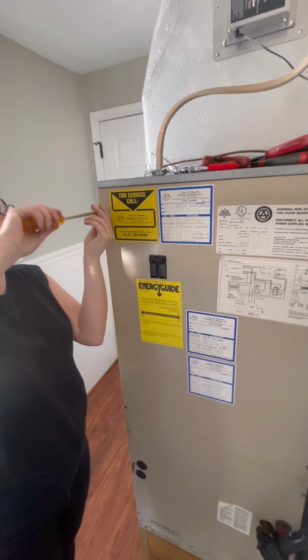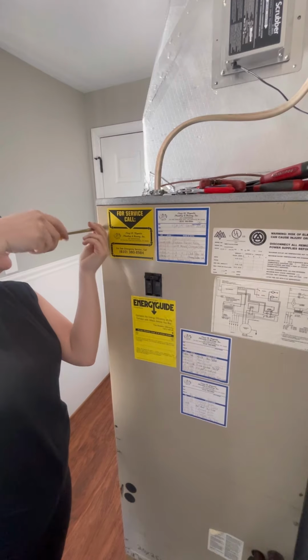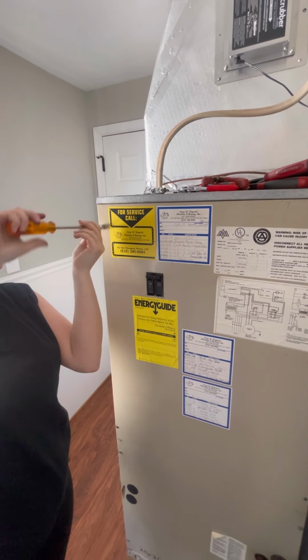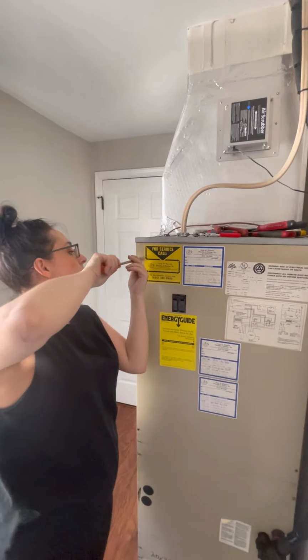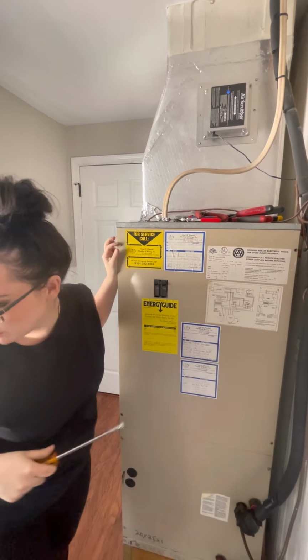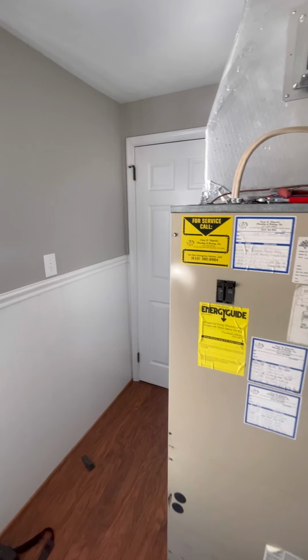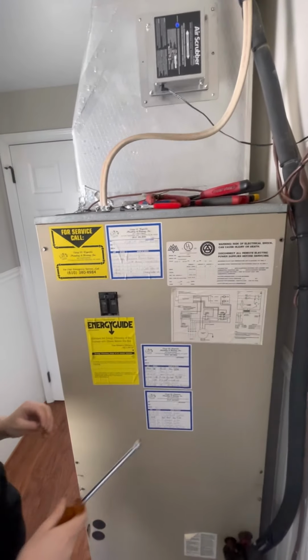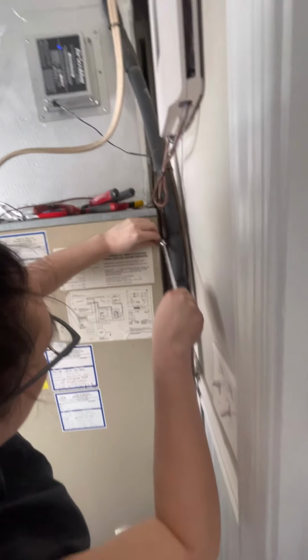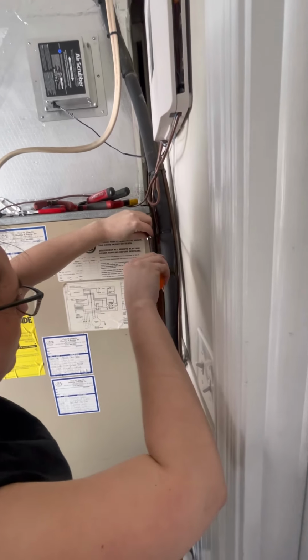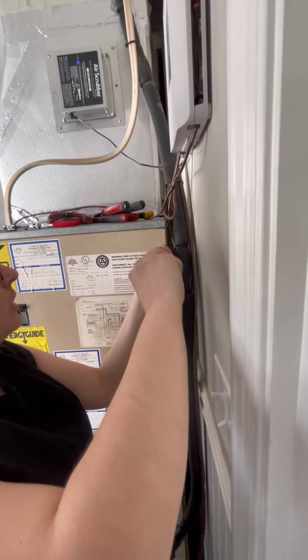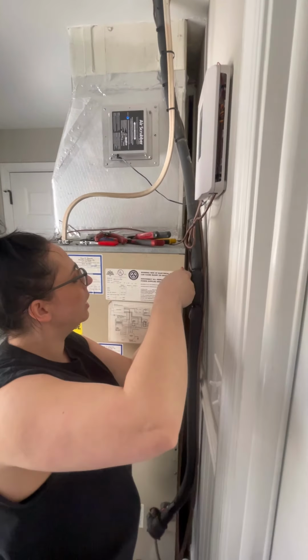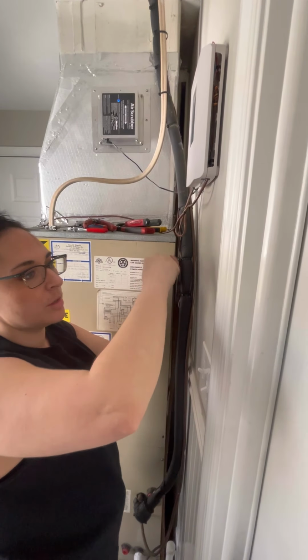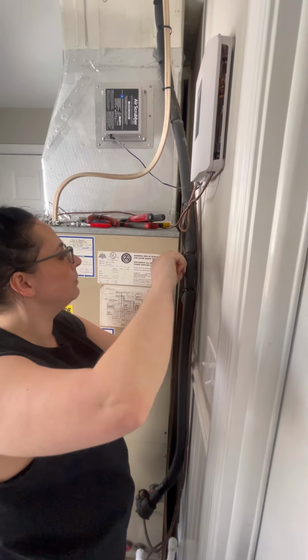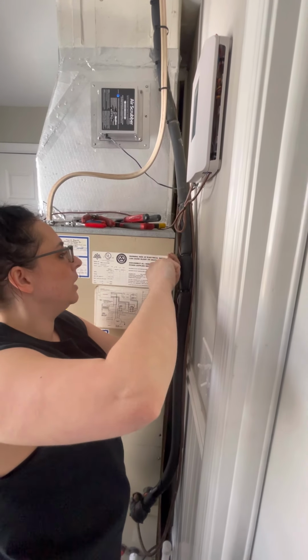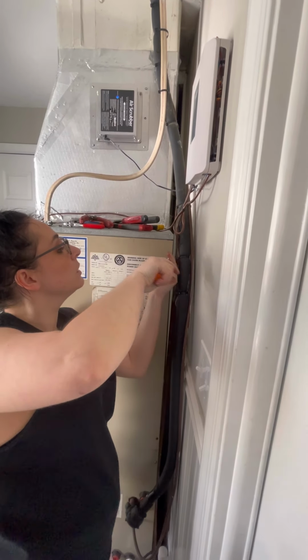Feel the vibration, alright. So we checked the coil for a refrigerant leak, we did not find any refrigerant leaks at this time. We checked the capacitor as well, and just checked the levels of that. Then I cleaned the blower, and then we found some issues with the electrical wires. We were able to save one by cutting off the bad portion of it, and fixing the wiring, then putting a 12 gauge on it.